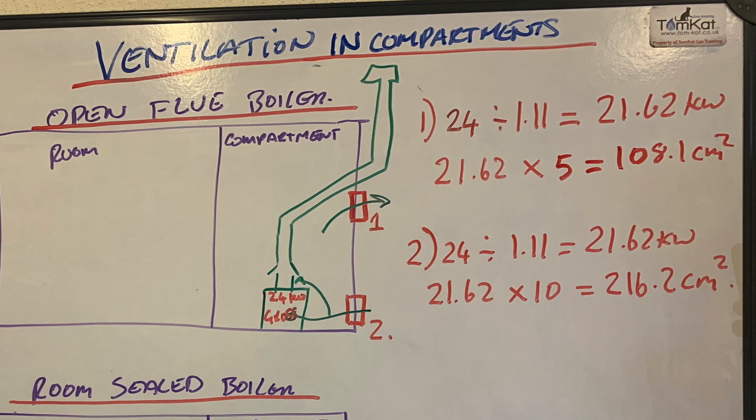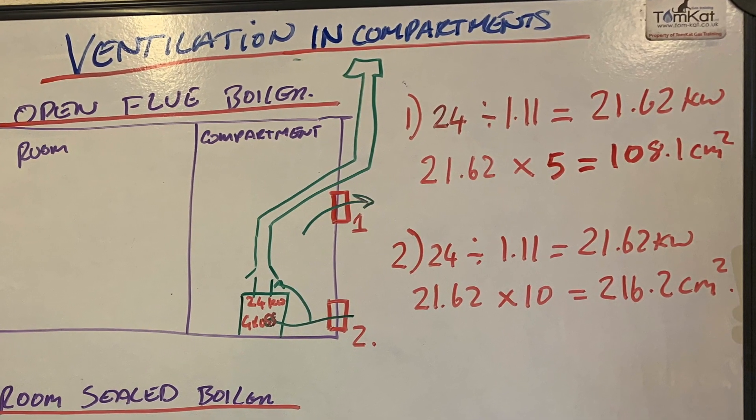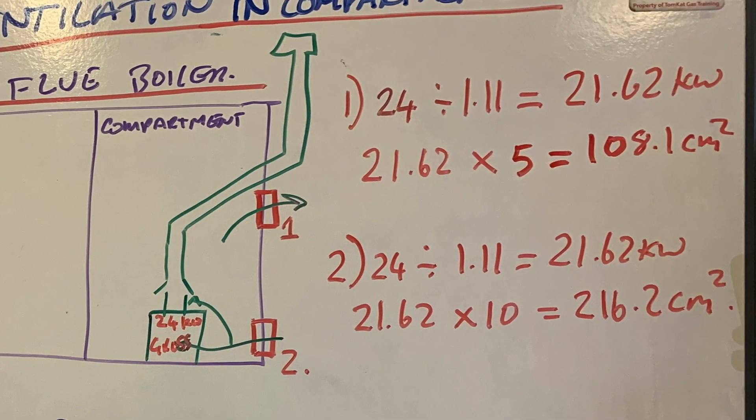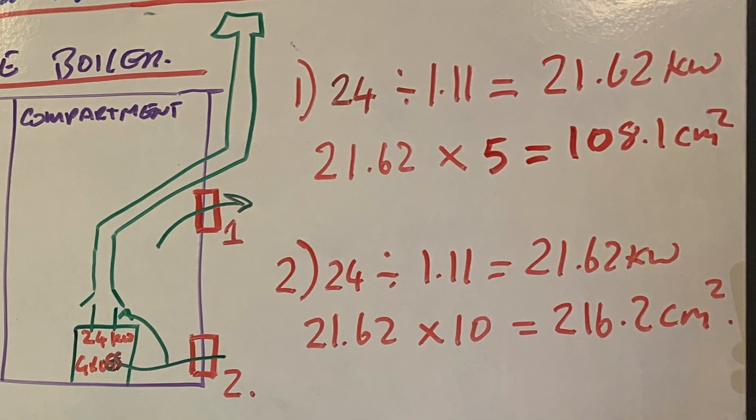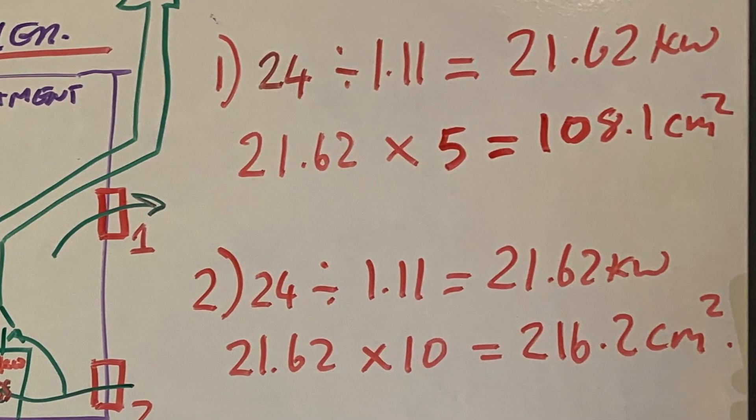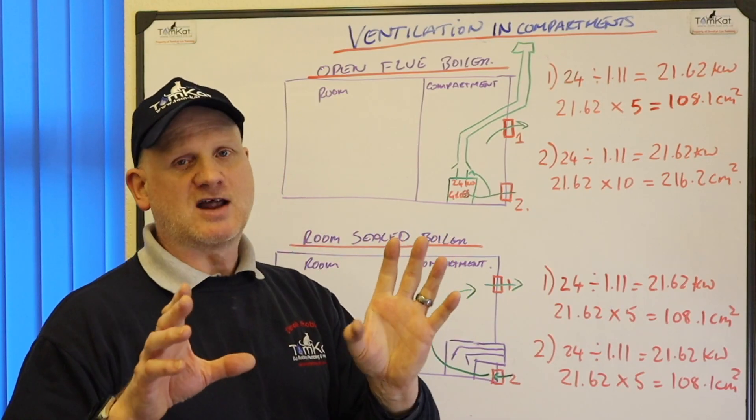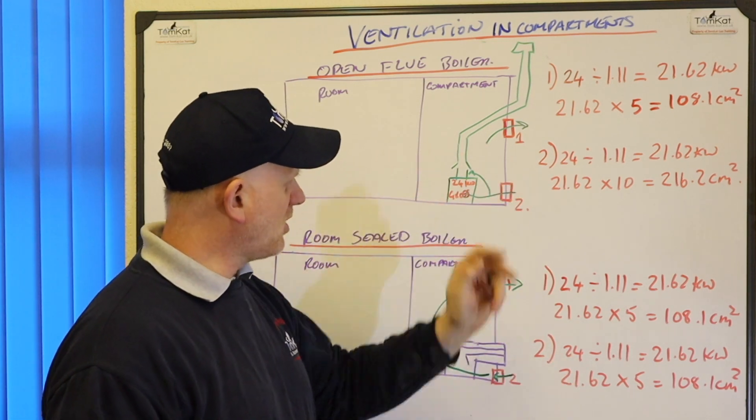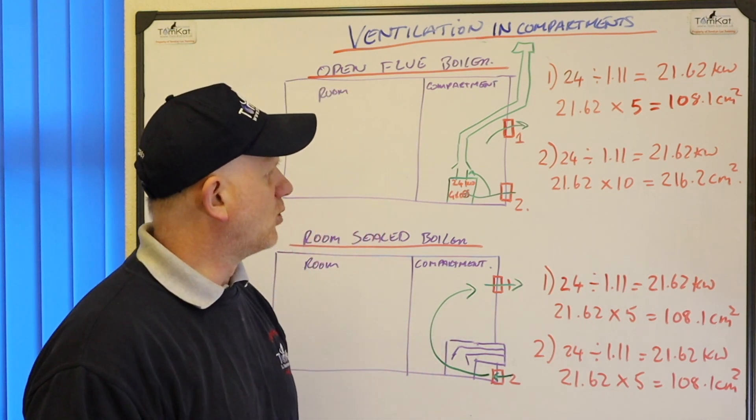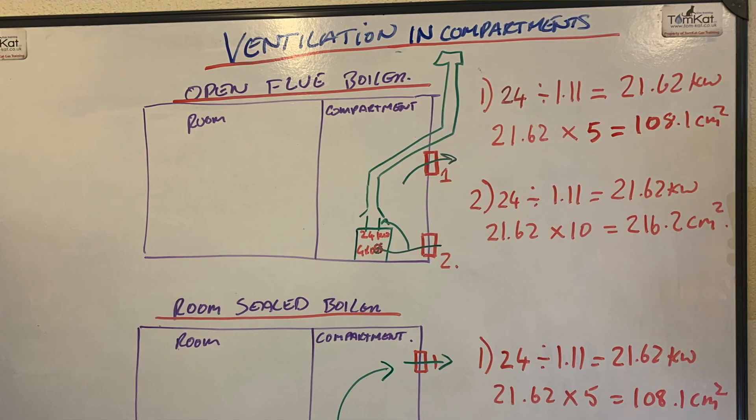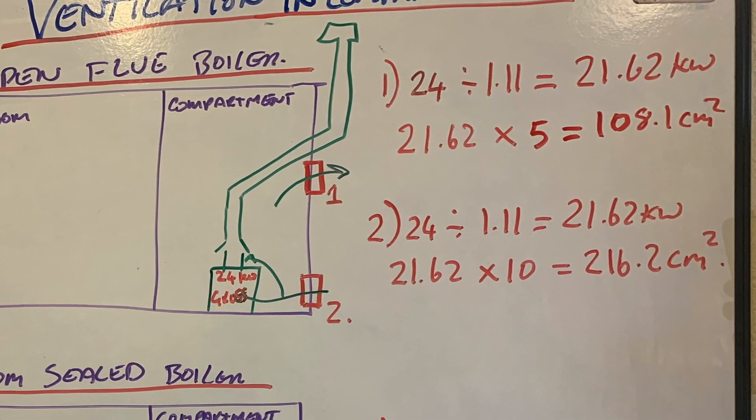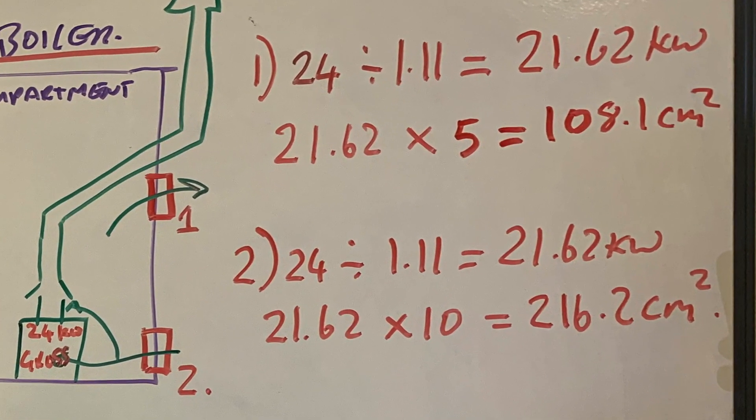So we need to do 24 divided by 1.11 is 21.62kW. Then we need for the top vent, because it's for cooling, we need to times it by 5. So it's 21.62 times 5 is 108.1cm². So that's your top vent, which is just mainly for cooling. Now your bottom vent, which is for combustion. So you've got 24 divided by 1.11 again is 21.62 because returning gross to net. And then we've got 21.62 times 10 this time, which is 216.2cm².